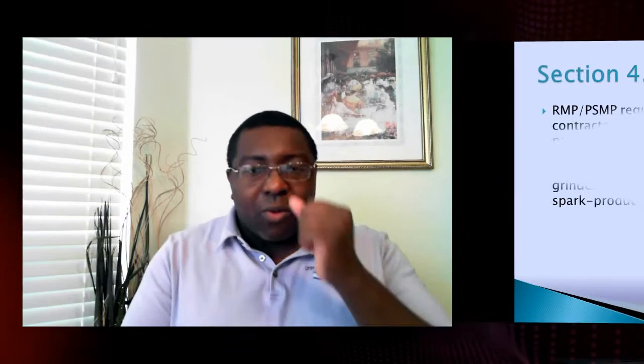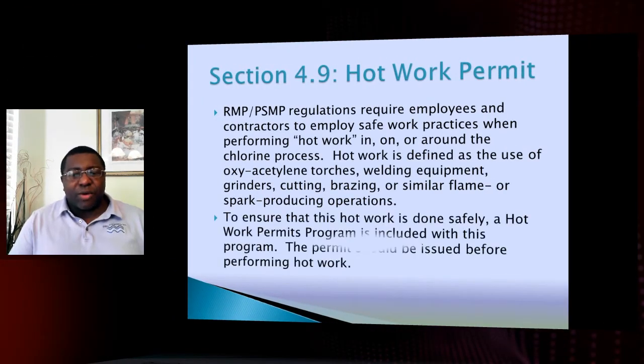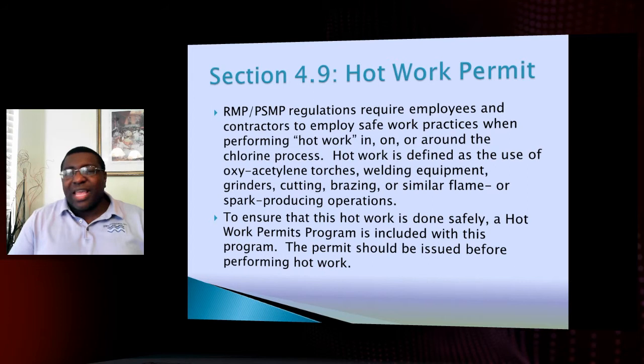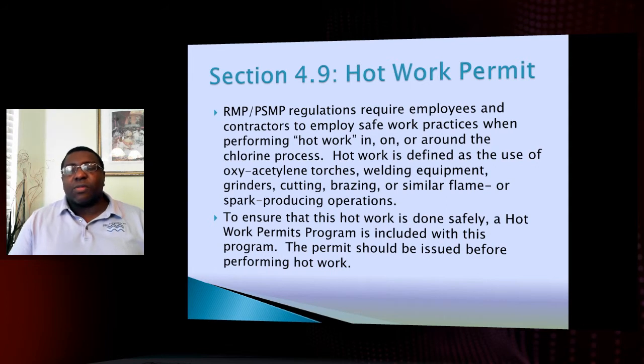Hot works permit: anybody working with any sort of brazing or welding around the chemical process could cause a reaction with the chemical. If there's hot work that needs to be done in that area, there should be a hot work permit, including a fire watch, which is 30 minutes after the hot work is complete, just to make sure there is no fire that could spread into your process area.